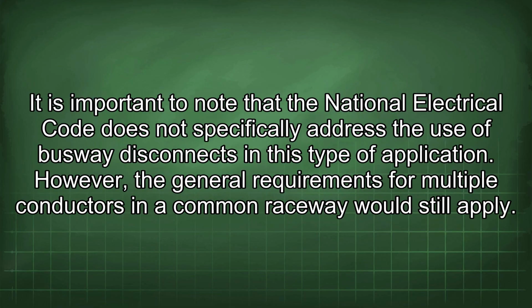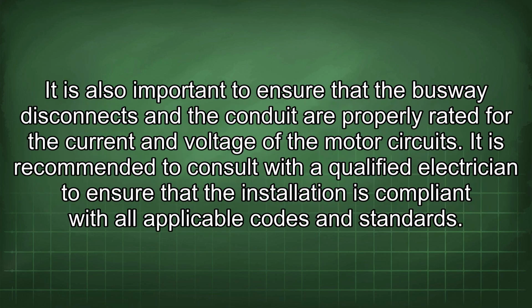It is important to note that the National Electrical Code does not specifically address the use of busway disconnects in this type of application. However, the general requirements for multiple conductors in a common raceway would still apply. It is also important to ensure that the busway disconnects and the conduit are properly rated for the current and voltage of the motor circuits. It is recommended to consult with a qualified electrician to ensure that the installation is compliant with all applicable codes and standards.